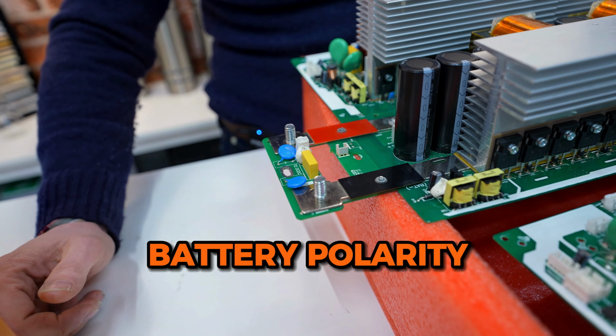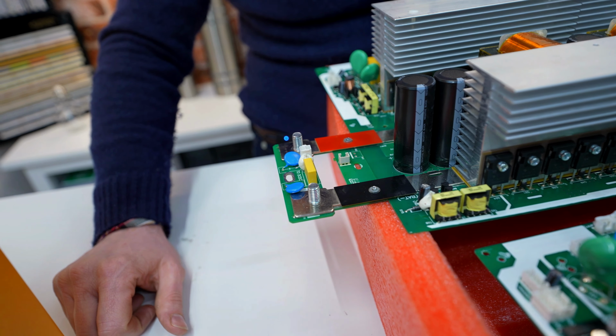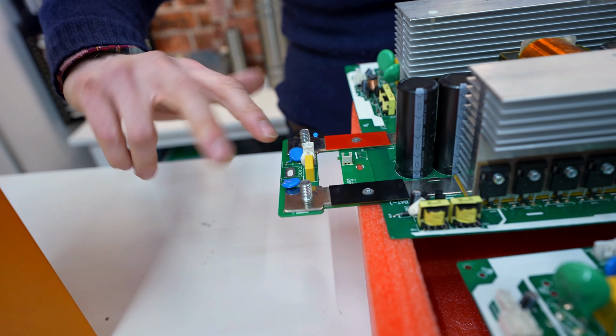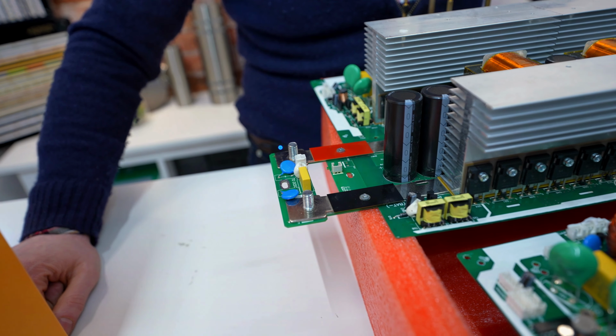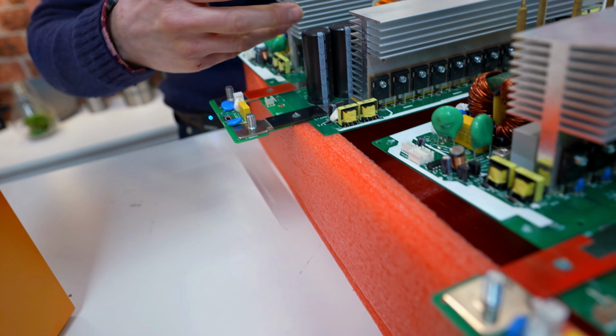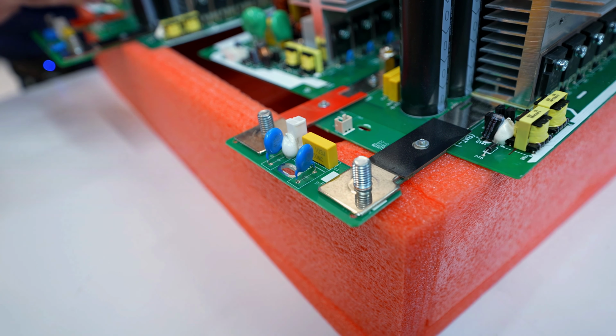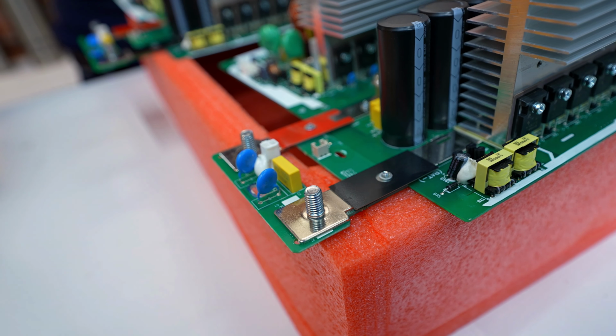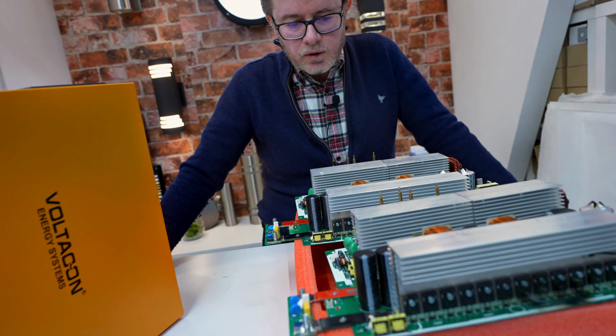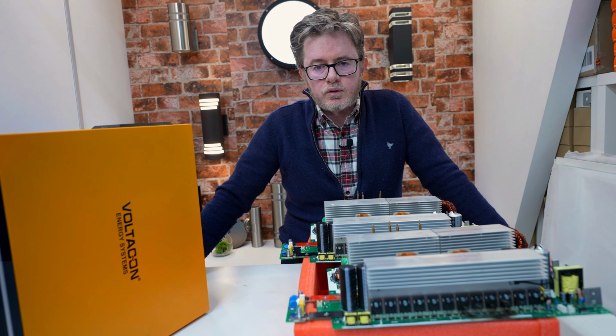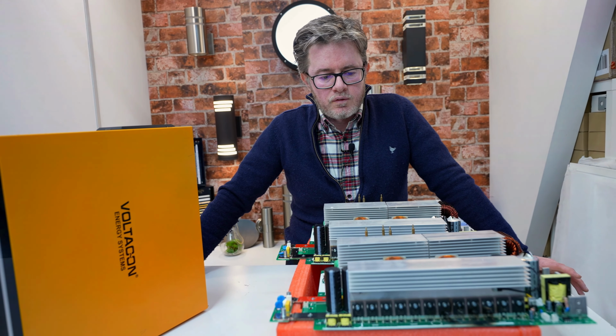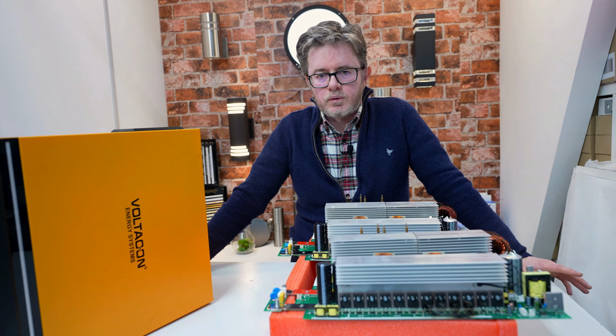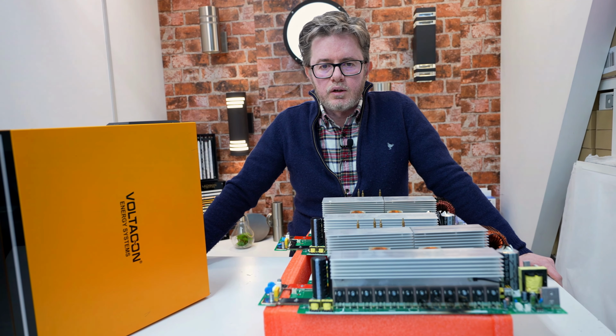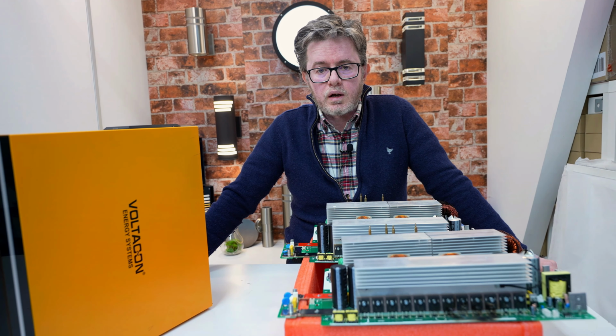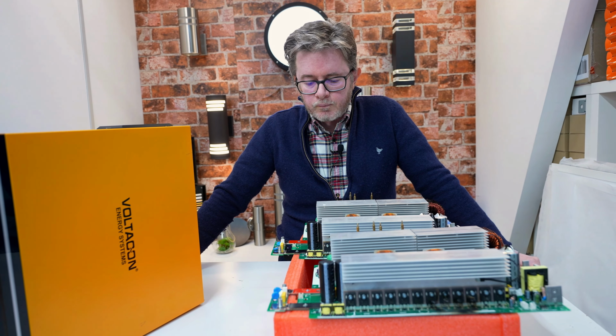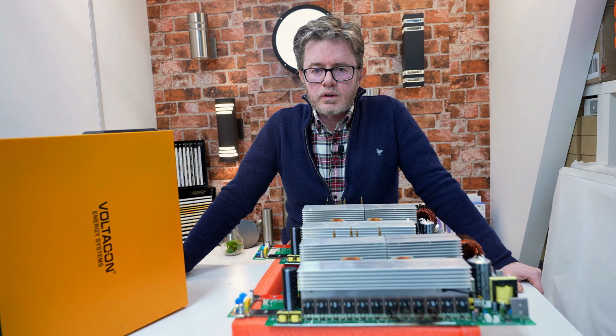We have cases when the customers get black cables, they are not color coded, and they reverse the polarity, and this can also blow up the capacitors or simply create a big short circuit at this point of the inverter. Unfortunately, the error 09, as you can understand, is not created by the inverter itself. It is 100% caused by an external factor, and for that reason the guarantee is not going to be covered by your supplier.